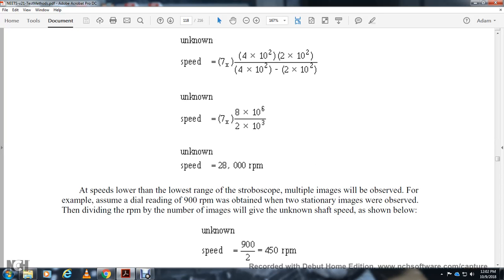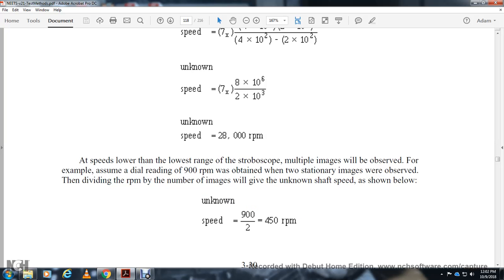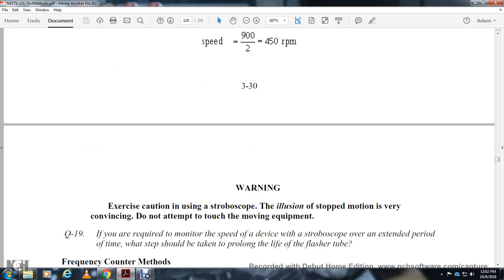If the speed is lower than the lowest range of the stroboscope, with multiple images seen by the observer, for example, assume a reliable reading of 900 RPMs was obtained with two stationary images observed. Dividing the RPM number by the number of images will give the unknown shaft speed. The unknown speed, 900 over 2, will give you 450 RPMs. Warning: exercise caution with the use of the stroboscope. The stop motion illusion is very convincing. Do not attempt to touch the moving equipment.